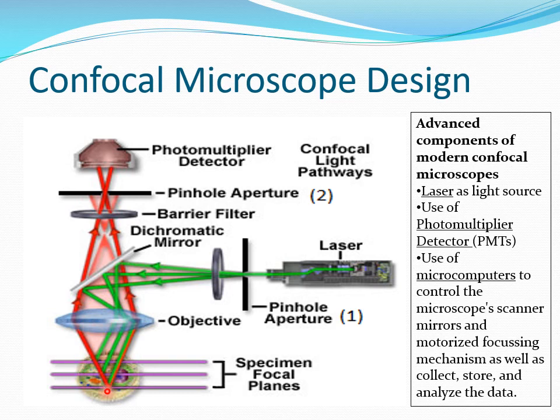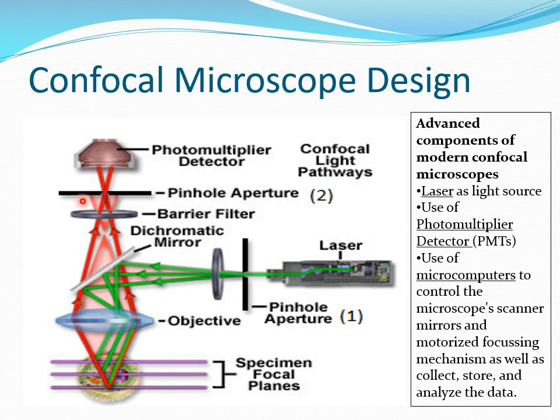The specimen has different fluorophores. When light is emitted back, it passes through a barrier filter, and another pinhole aperture or pinhole filter is placed in front of the photomultiplier detector. This photomultiplier detector is essential because it captures very weak signals. The pinhole aperture filters off all the noise — that is, all the rays except for the rays emitted by the specific segment or specific point that is our focus.